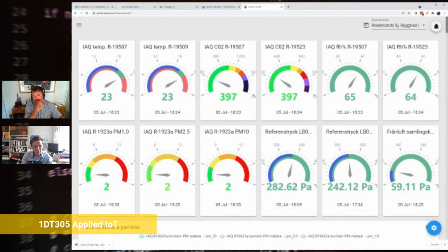What we see here is room temperature. You have a set point, which is the blue pointer, and a green sector showing the allowed range. If it goes into red, it creates an alarm. You also have CO2 values, relative humidity, and particulate matter—how much dust or particles are in the air we breathe. This is in Stockholm; sometimes it's very dirty. And this is the pressure in the ventilation unit.